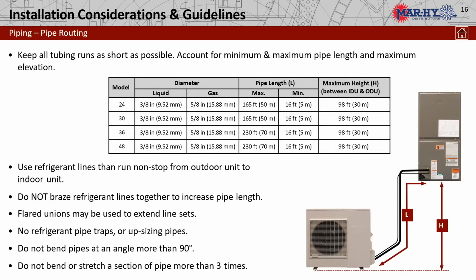One thing that RUUD suggests is that we do not braze to extend our lengths on line sets. They'd rather have you use a flared union, torqued to the proper specs to eliminate any oxidation or any other contaminants that may be available if you're brazing. Now, that's not to say you can't do it if you do the proper procedures. Obviously, if you nitrogen purge and you make sure you don't pour a bunch of solder into the piping, you wouldn't have any problem. Standard 3/8, 5/8 brazing, we do it all the time, right? That's what we do for a living.